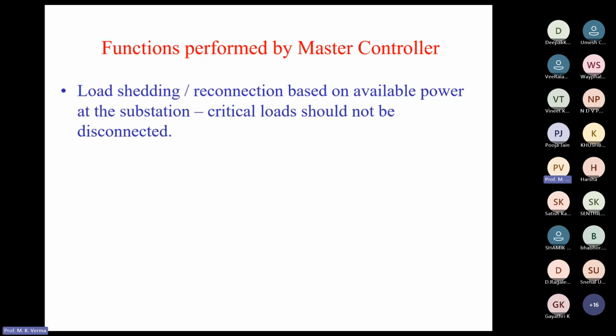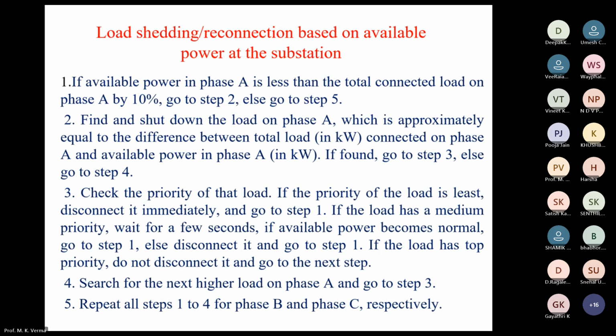The function performed by the master controller was load shedding and reconnection based on power available at the substation, without disturbing critical loads. So he developed an algorithm for load shedding and reconnection: if the available power is less than some value, then you should disconnect some loads, and when the available power increases, then you should reconnect them.